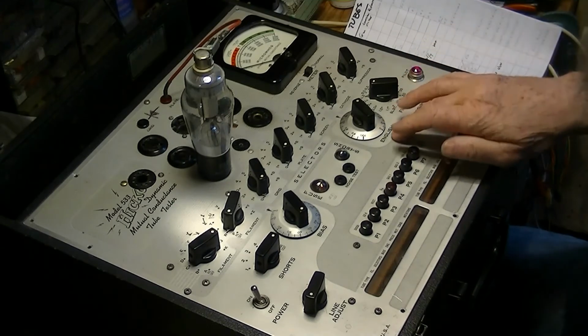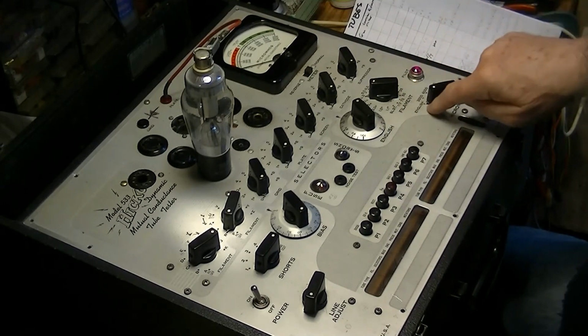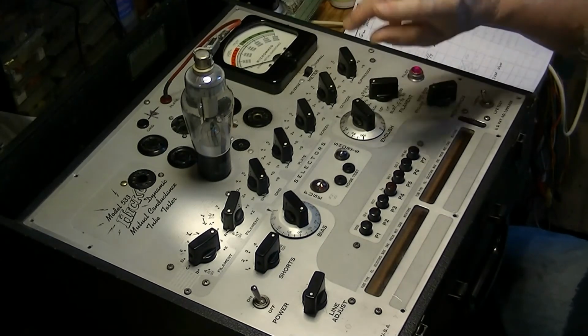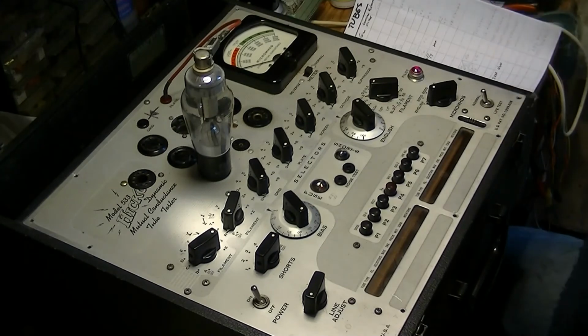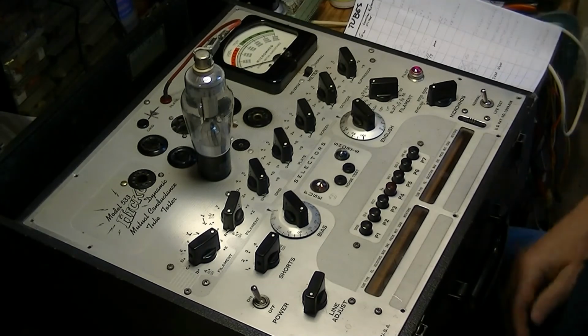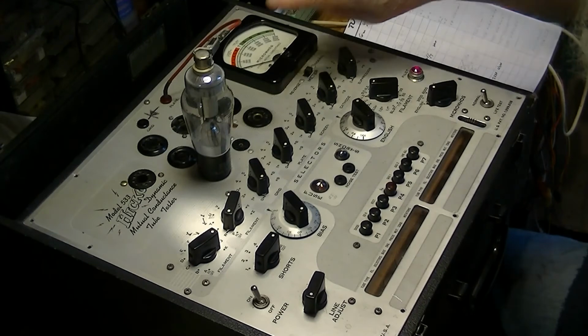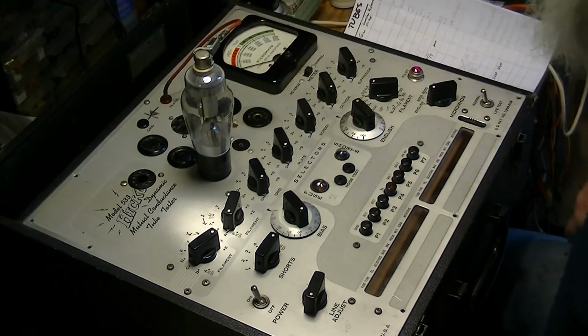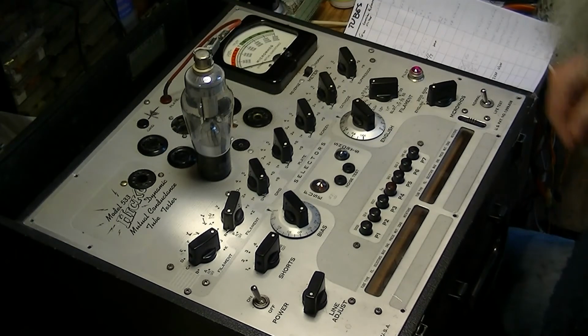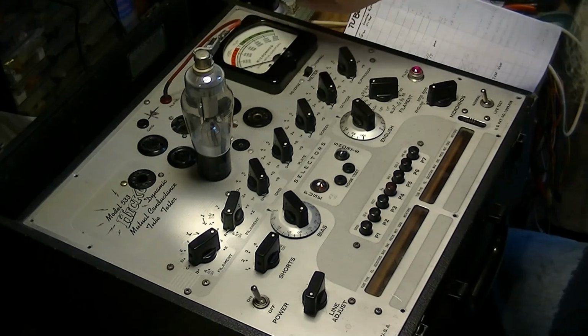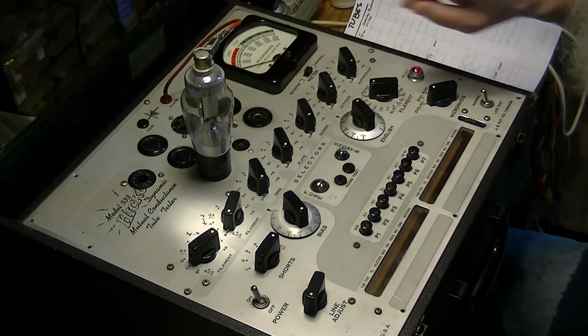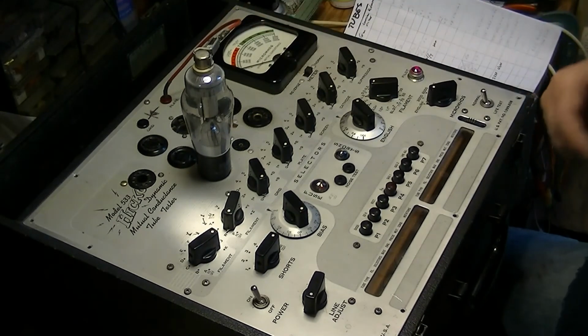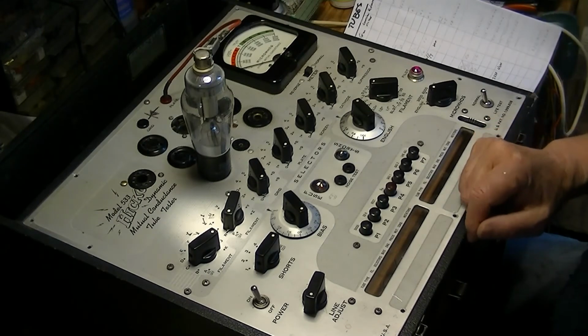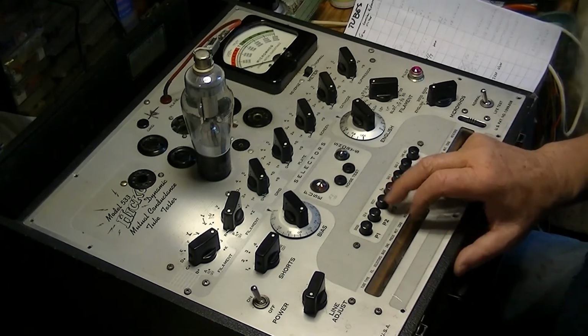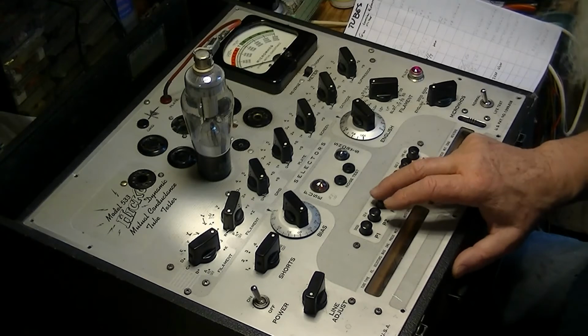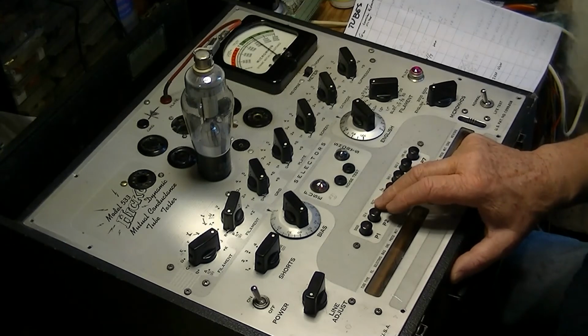Again, you set the load, you put this in the English position, which is the good bad reading on the meter, and that's all you're going to get. You get a relative look at the amplification in a tube that amplifies. On this one, you're just going to get a look at how well it conducts. So I'm going to go ahead and test this now. I'll push P3, the rectifier test button, and it goes up in the green.